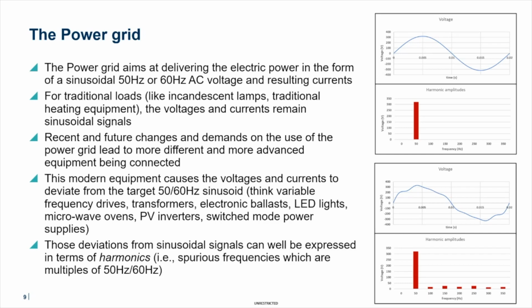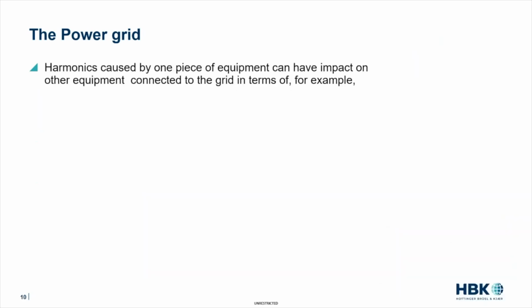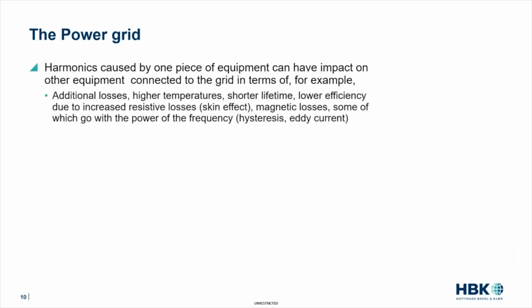So this distortion, or those spurious frequencies, are generated by certain devices or equipment connected to your power grid. But if I connect another device, this device will no longer see a perfect sine wave. It will see a time signal as depicted in this slide. So harmonics caused by one piece of equipment can have an impact on other equipment connected to the grid. If you have harmonics in your power signal, this will lead to additional losses, and those additional losses will lead to higher temperatures. Those higher temperatures may lead to shorter lifetime, lower efficiency, etc.